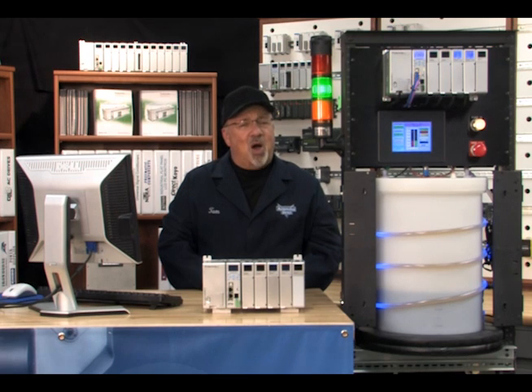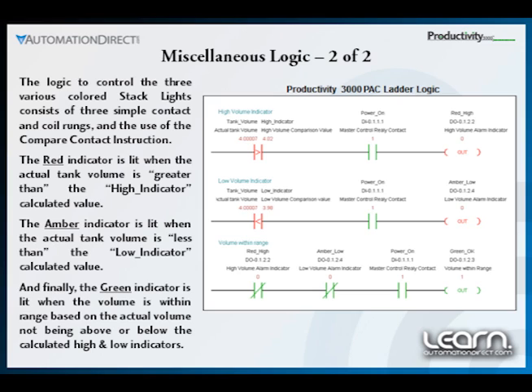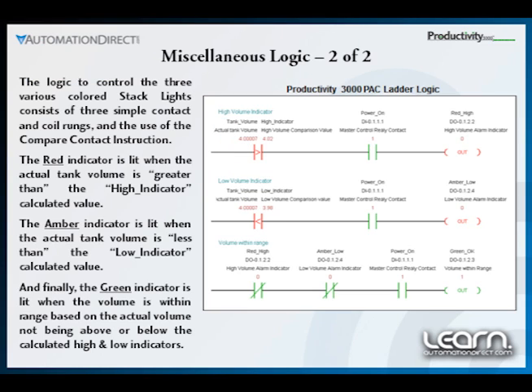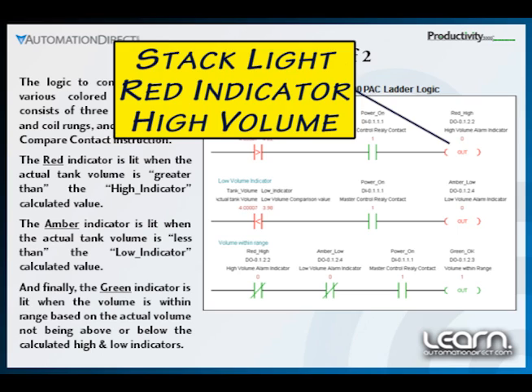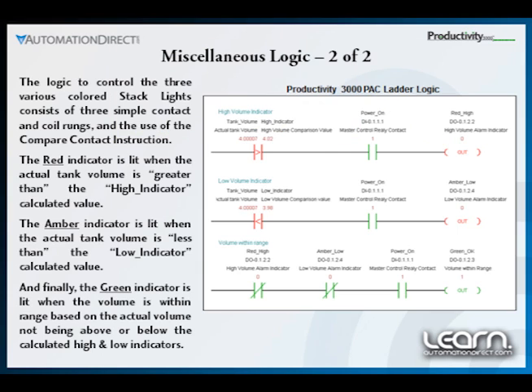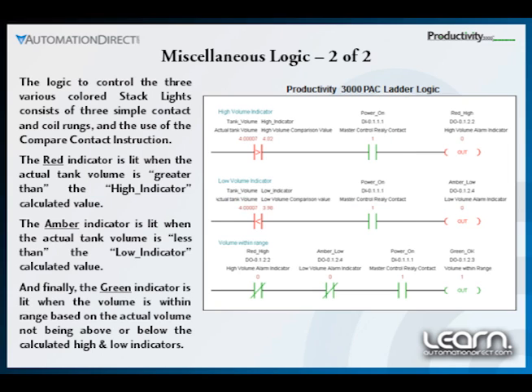With some additional simple ladder logic programming using the Productivity 3000's Compare Contacts, we can have the three colored stack lights indicating our process tank's volume status. The red indicator is lit when the actual tank volume value is greater than the tag name High Indicator, and the amber indicator is lit when the actual tank volume is less than the tag name Low Indicator. Finally, the green indicator is lit whenever the volume is neither greater than the High Indicator value nor less than the Low Indicator value.